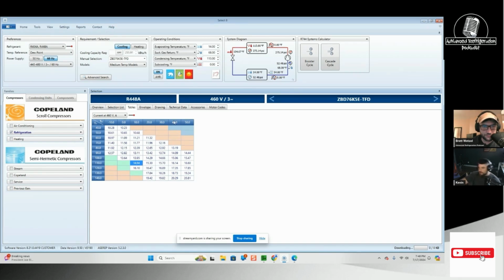So if you look here, you've got temperature condensing. If you went to say 110 degree condensing and you were running a 20 SST, you should be at 15.35 amps. If you were running a 70 degree condensing and you were 20 degree saturated, you're going to be at 11 amps. Same thing, if you went to a 30, you're going to go up slightly at 110.